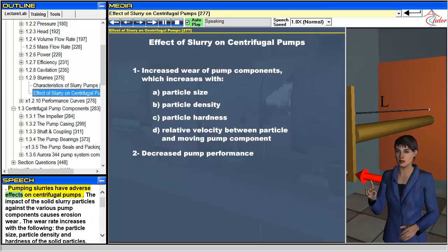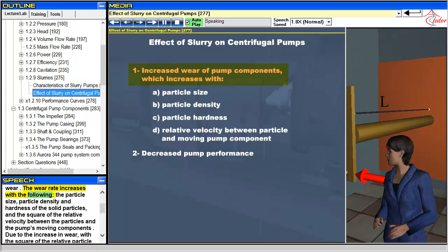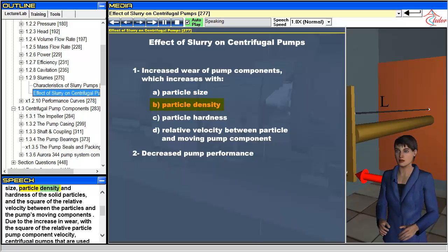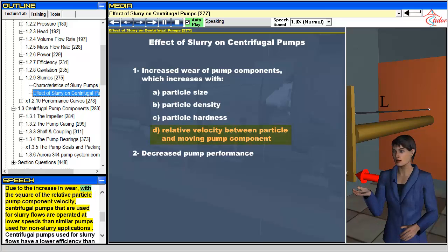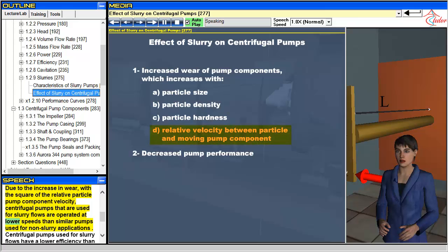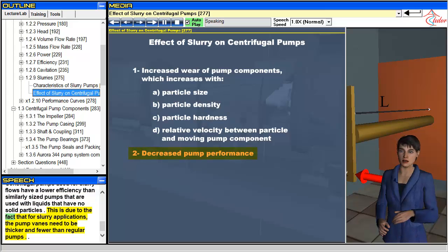Pumping slurries have adverse effects on centrifugal pumps. The impact of the solid slurry particles against the various pump components causes erosion wear. The wear rate increases with the particle size, particle density and hardness of the solid particles, and the square of the relative velocity between the particles and the pump's moving components. Due to the increase in wear with the square of the relative particle-pump component velocity, centrifugal pumps used for slurry flows are operated at lower speeds than similar pumps used for non-slurry applications. Centrifugal pumps used for slurry flows have a lower efficiency than similarly sized pumps used with liquids that have no solid particles, due to the fact that the pump vanes need to be thicker and fewer than regular pumps.